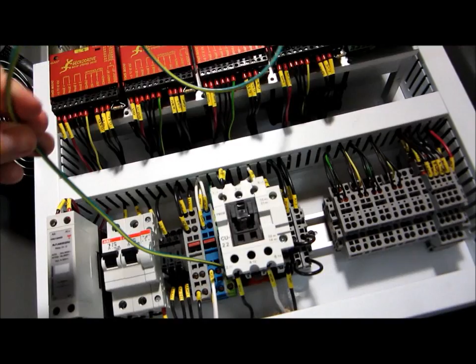I've also got jumpers to complete my e-stop circuit for now, because there's no field connections at this point, just sitting on the bench. But coming in, I've got my terminals here for X, Y1, Y2, and Z, and then the potential, even though I didn't pre-wire it, I've got everything in place to wire that fifth guy in there. These are also my 4 proximity sensors, the 8mm proximity sensors, and then here's my 2-tier terminal for my aluminum touch plate or any other kind of touch plate device on the machine, which is wired up to the PMDX.